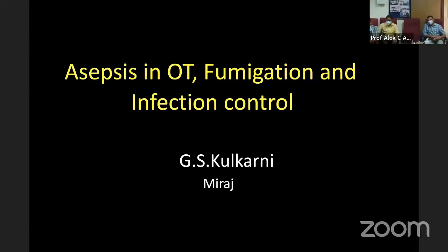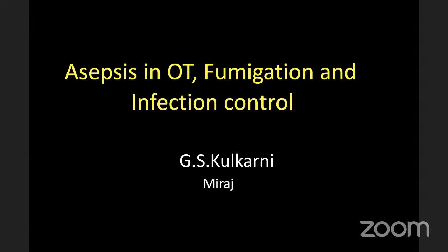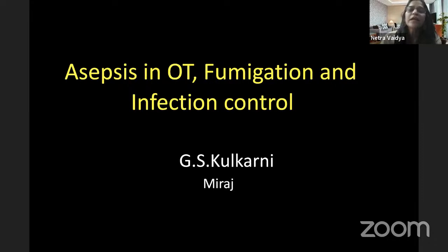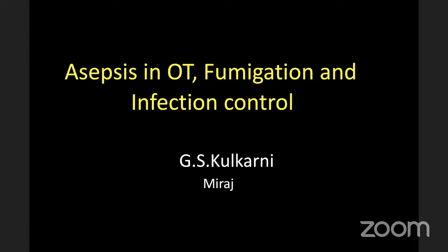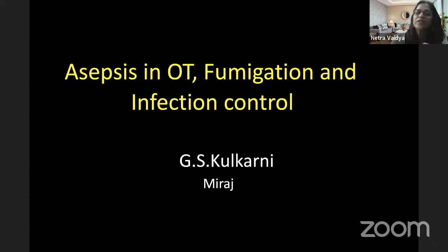Madam, in small hospitals, it is usually drums with a vertical autoclave which I use. And usually they do it once in a week. So is it a good practice or do they have to change it? See, the whole point in using drums is that it does not have a covering. You have openings over there to allow the steam to penetrate. You close it after sterilization.